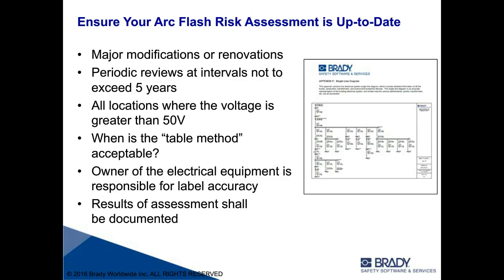As we said before, it's also very important to remember that all locations where voltage is greater than 50 volts need to be labeled. I've been to a lot of facilities where they might have panel boards and motor control centers labeled, but they miss a lot of disconnect switches or industrial control panels. In many cases, the control panels are things that get opened up, and the troubleshooting activities happen there quite a bit more frequently than they would at a panel board. So there is a lot of risk at anything 480 volt, 208, 240, and those things should be included in the assessment.